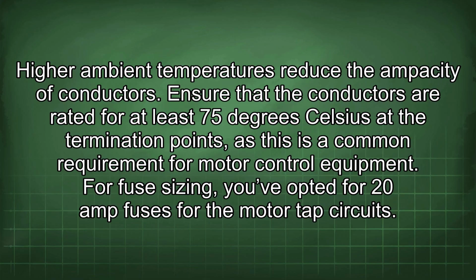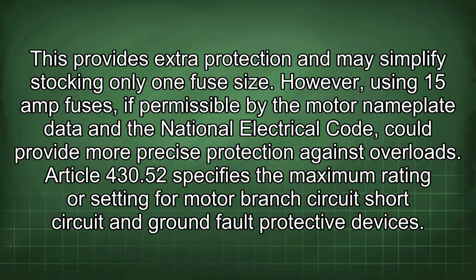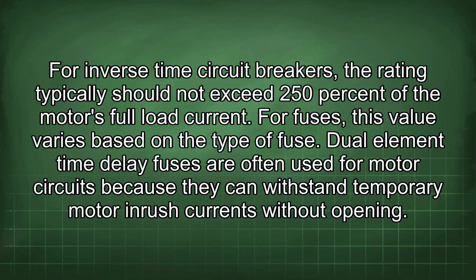For fuse sizing, you've opted for 20 amp fuses for the motor tap circuits. This provides extra protection and may simplify stocking only one fuse size. However, using 15 amp fuses, if permissible by the motor nameplate data and the National Electrical Code, could provide more precise protection against overloads. Article 430.52 specifies the maximum rating or setting for motor branch circuit, short circuit, and ground fault protective devices. For inverse time circuit breakers, the rating typically should not exceed 250% of the motor's full load current. For fuses, this value varies based on the type of fuse.